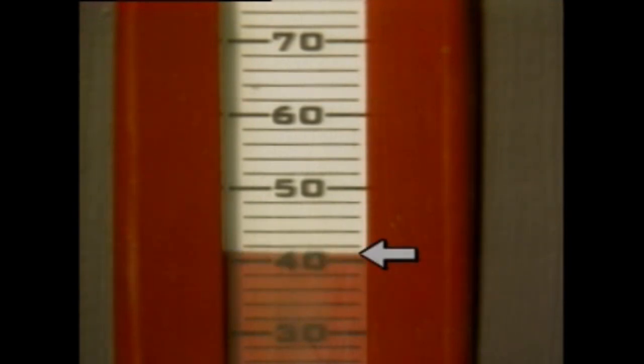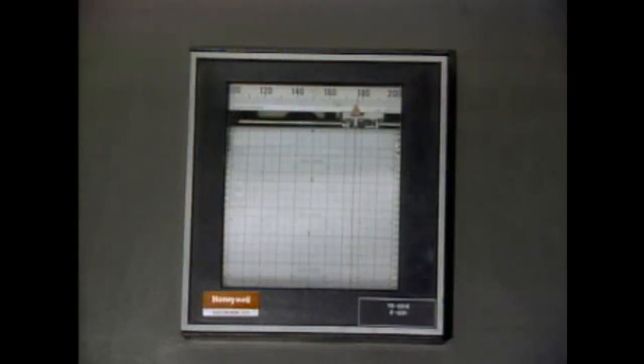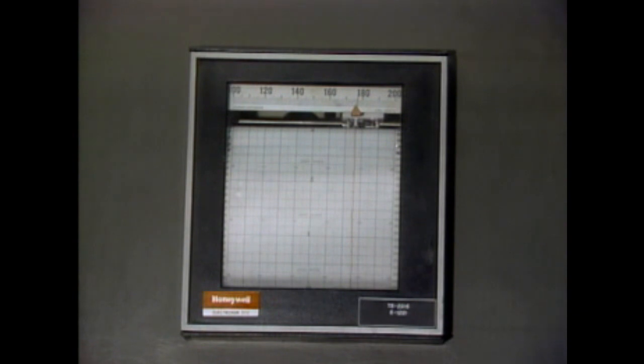If the indication of a value falls between two subdivision marks, it's usually okay to estimate the reading by selecting a number between the two subdivision values. Indicators and gauges both indicate the value of a process variable at the time of the reading. But another instrument, a recorder, indicates the present value of a variable and provides a continuous permanent record of the value over a given period of time.